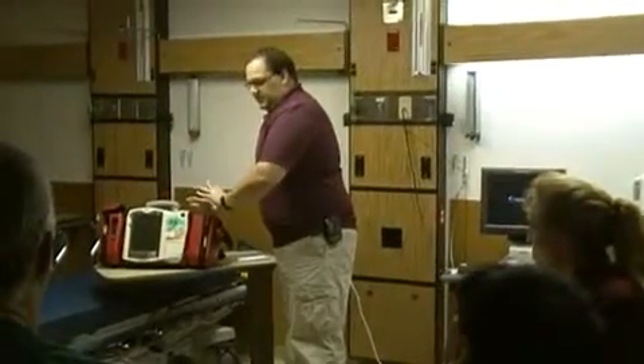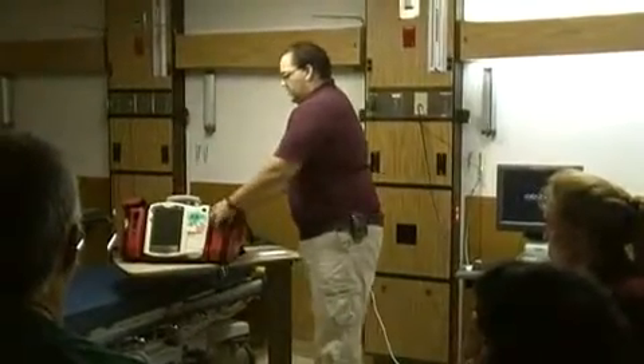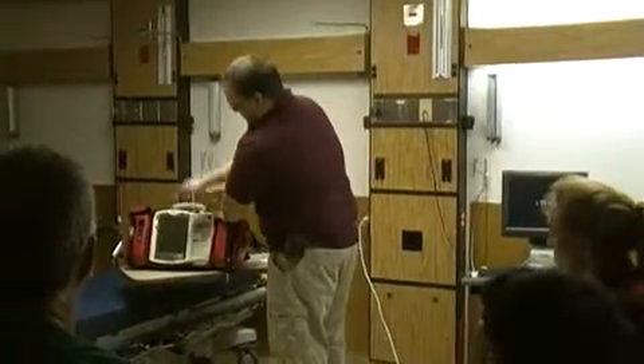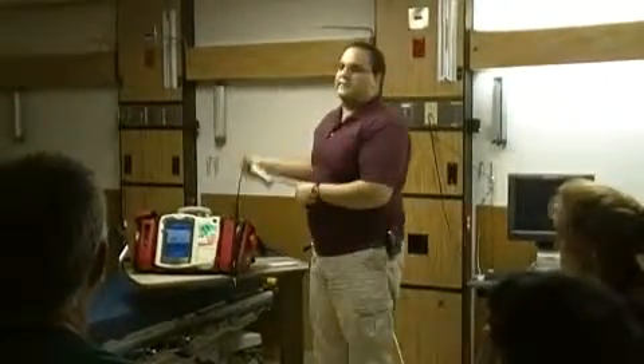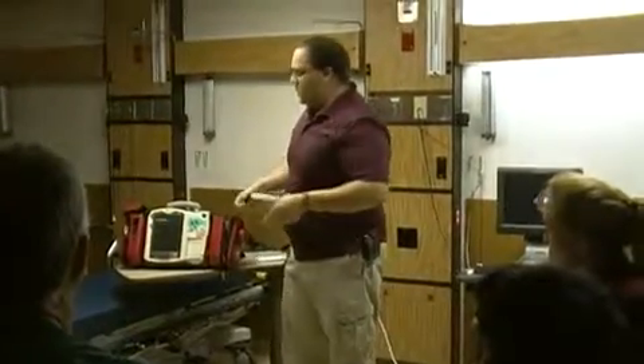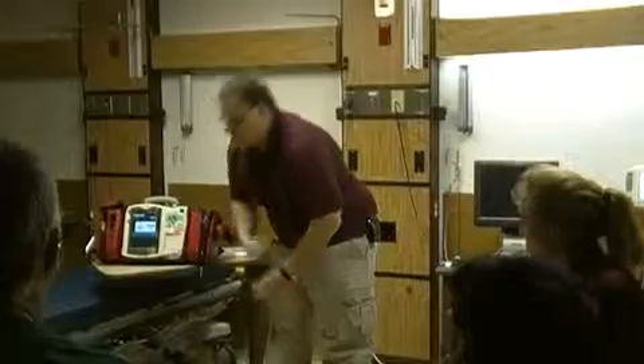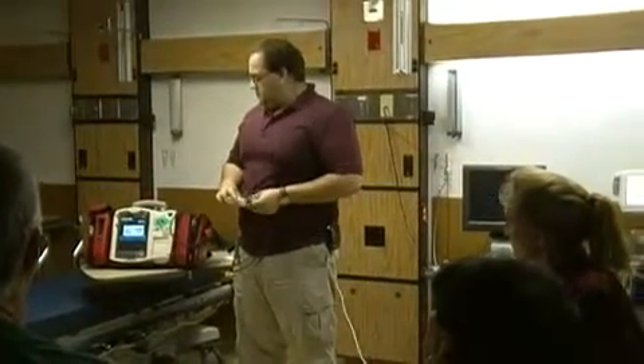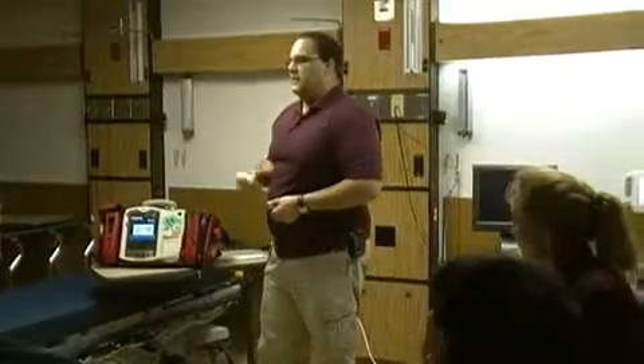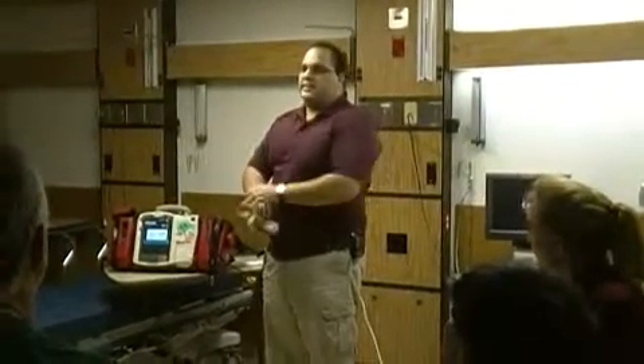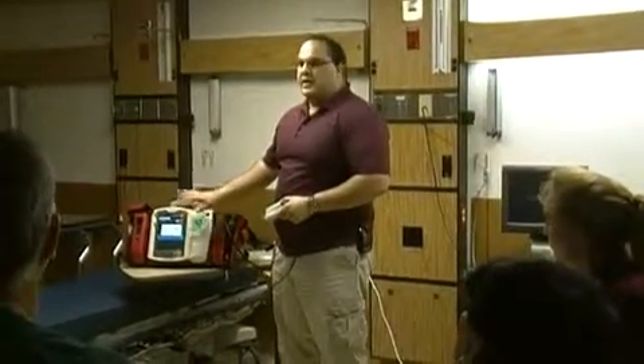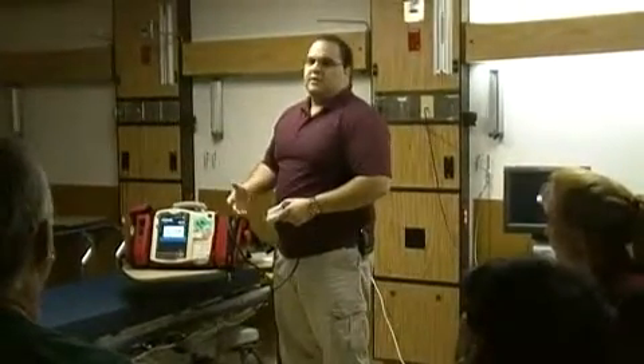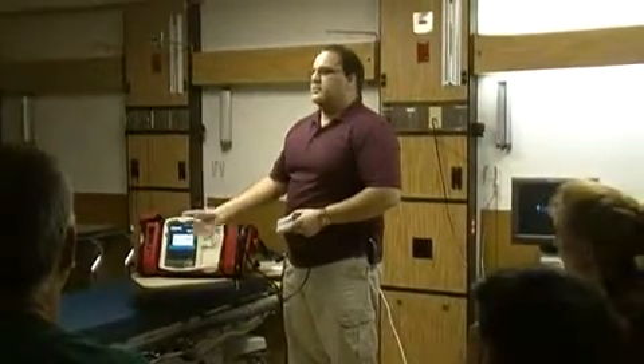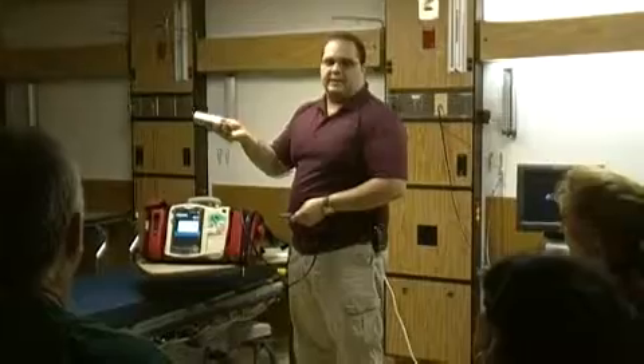These red accessory pieces right here do come extra. But to defib, there's a couple ways. You can automatically turn it over to the left to the AED mode, which it'll talk you through the steps. Apply pads to patient's bare chest. Plug in pads connector. Due to safety concerns, even though there are services in Arizona that are defibrillating through CPR compressions, as of yet, it has not officially been determined as safe. And the electricity, the joules that go through the monitor defibrillator can actually be passed on to a bystander or rescuer. So if there's any chance of electricity, don't touch the patient, don't touch anything conductive.